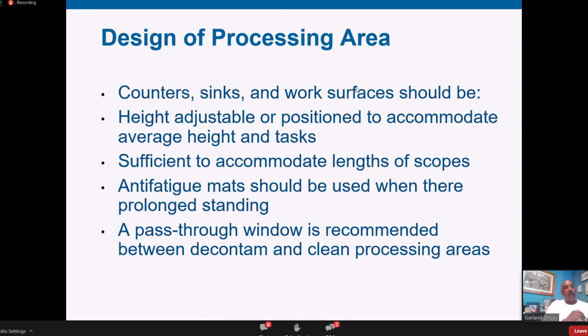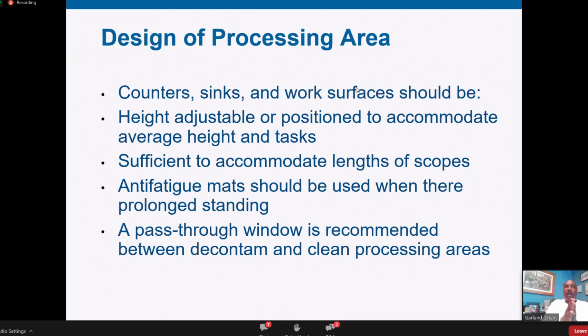Your clean processing area, where your AERs may be, or your storage area, should be positive air. You don't want to mix the two. There's some air balancing done in certain facilities - some newer facilities are monitored by engineering departments, some facilities monitor their own airflow and air balance. But basically the difference is kind of like washing dishes - you have your clean side and you have your dirty side.